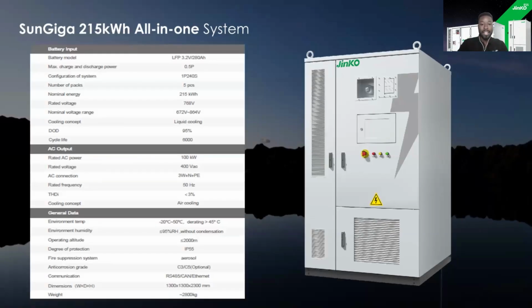So here's the spec sheet for the 215 kilowatt hour system. It uses a 280 amp hour cell size. Currently, we will be moving on to a larger cell size, which is a 314 amp hour cell. That was self-developed again by Jinko, and we're producing our own cells for that as well. And you'll learn a bit more about the cell a bit later once I pass to Lucia. It's a 0.5 C system, so it's a 2-hour system for charge and discharge.